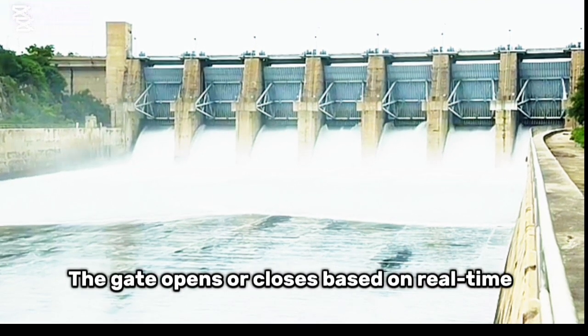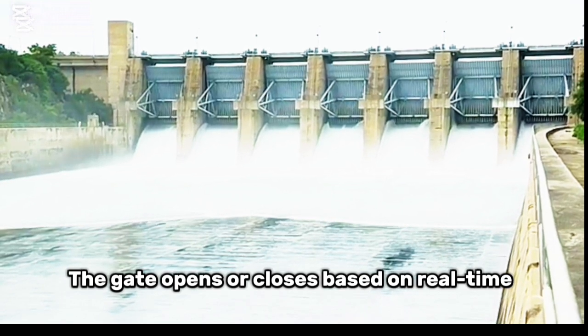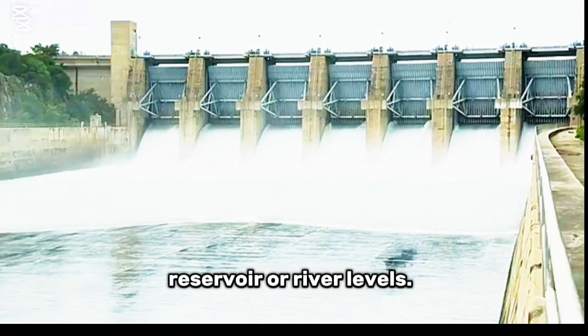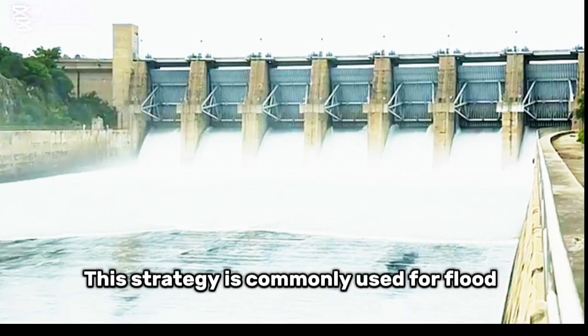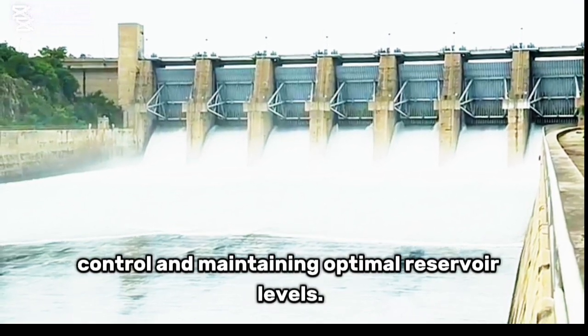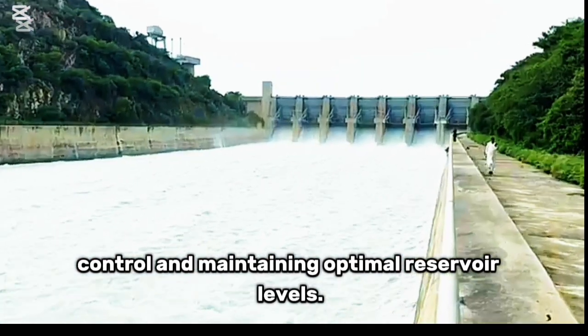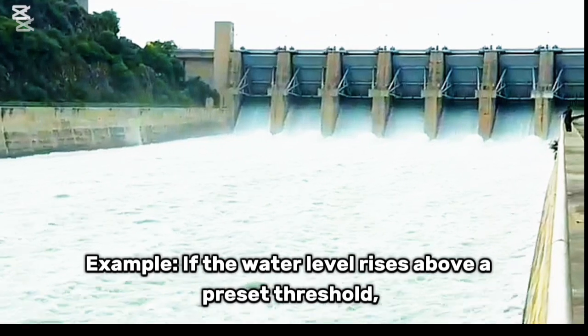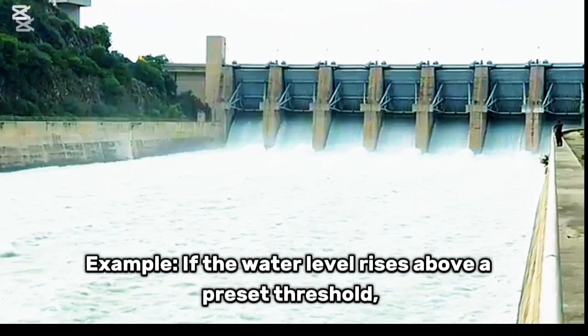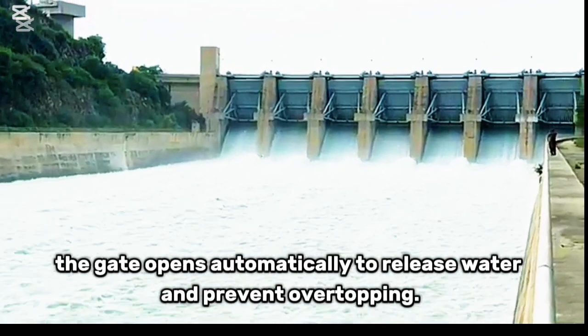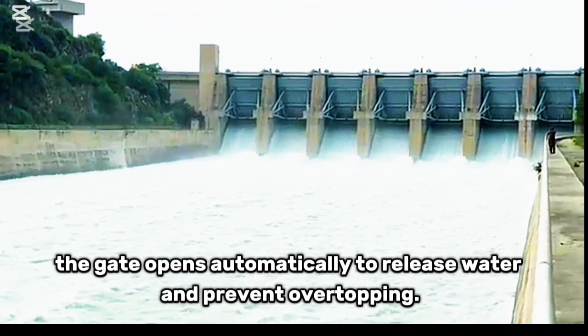Types of SCADA control strategies. Level-based control. The gate opens or closes based on real-time reservoir or river levels. This strategy is commonly used for flood control and maintaining optimal reservoir levels. Example: if the water level rises above a preset threshold, the gate opens automatically to release water and prevent overtopping.